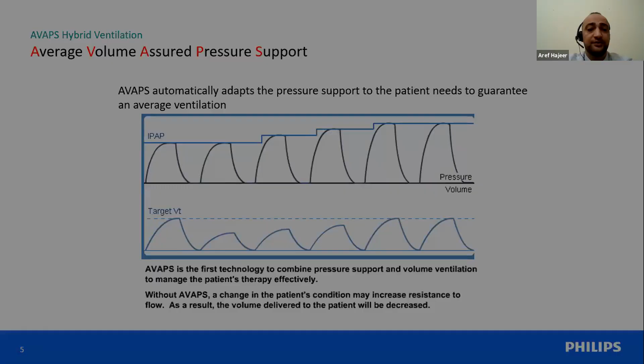And without Avaps, if the patient has a change in their tidal volume frequently, the tidal volume which will be delivered to the patient, especially if using pressure modes of ventilation where you don't have any control on the tidal volume, will not be fixed all the time, and it will cause the ventilation to fail for the patient. Now, let's talk about the Avaps therapy in detail.